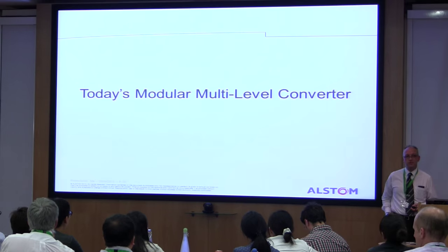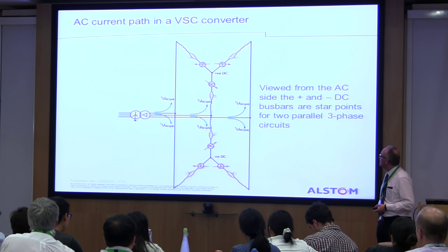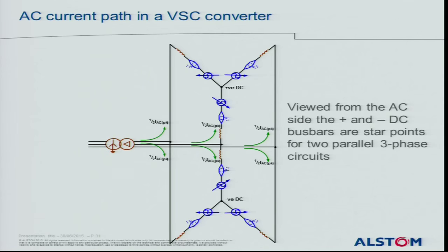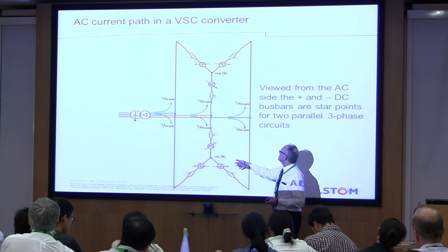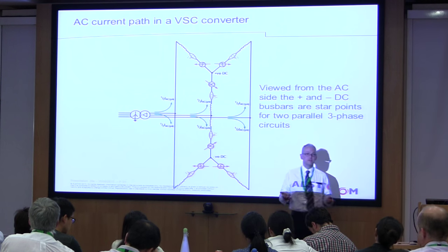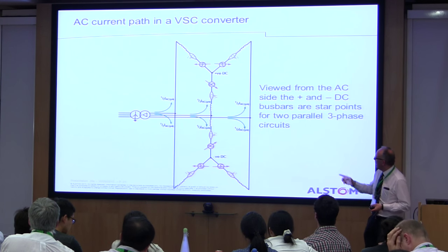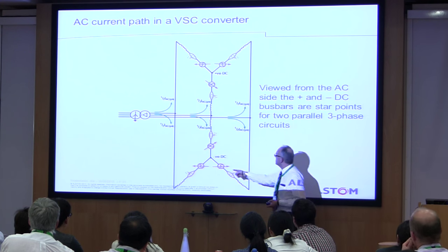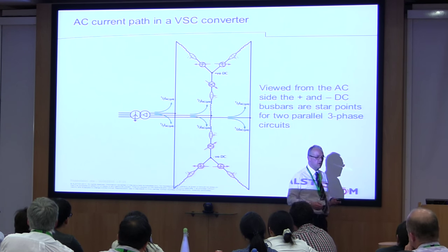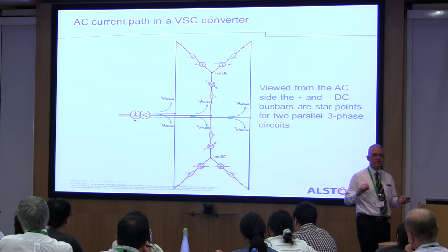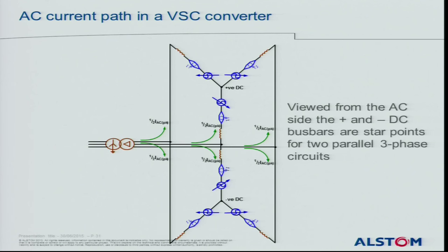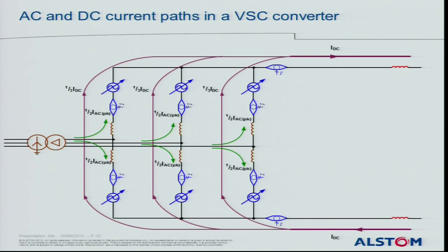Today's modular multi-level converter — basically, if you take two STATCOMs, each with three power converter valves interconnected in a star arrangement, and put two of those in parallel without grounding the neutral point, you can generate a voltage difference between those neutral points. If you redraw the circuit, you've got an HVDC converter — it's the same circuit.